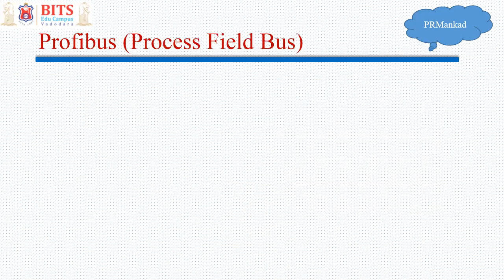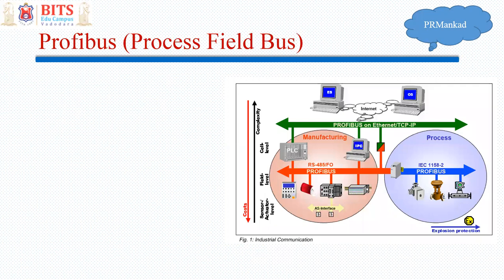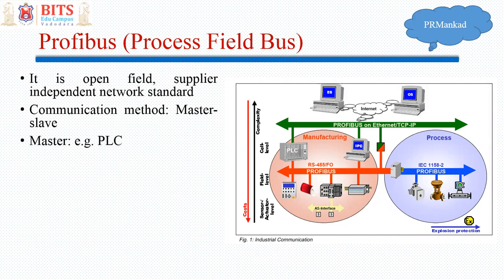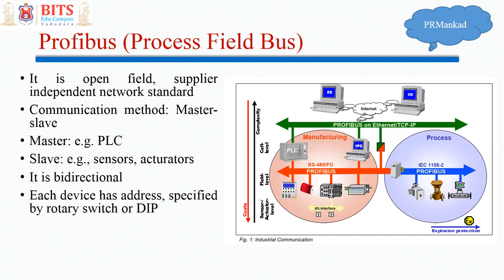The next very popular and commonly used field bus is Profibus — short for Process Field Bus. Profibus is compatible with various communication standards like RS-485, IEC 1158-2, Ethernet, and so on. From around 2000 onwards, it became an open, supplier-independent network standard. It communicates based on master-slave architecture — generally PLCs are masters and sensors and actuators are slaves. It supports bi-directional control and each device has an address specified by a rotary switch, with up to 127 devices connectable.